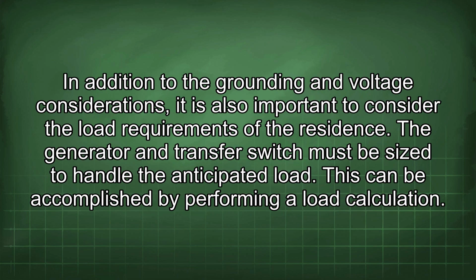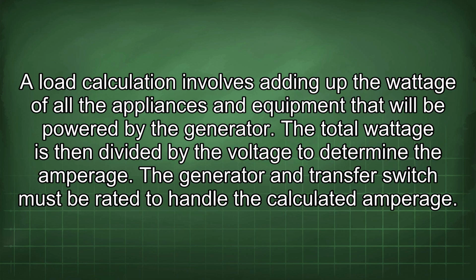In addition to the grounding and voltage considerations, it is also important to consider the load requirements of the residence. The generator and transfer switch must be sized to handle the anticipated load. This can be accomplished by performing a load calculation. A load calculation involves adding up the wattage of all the appliances and equipment that will be powered by the generator. The total wattage is then divided by the voltage to determine the amperage. The generator and transfer switch must be rated to handle the calculated amperage.